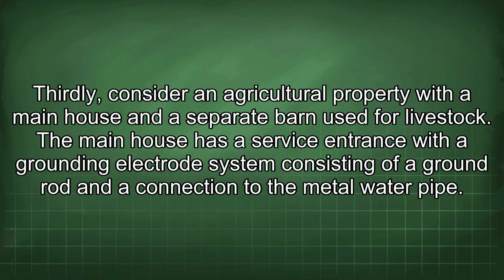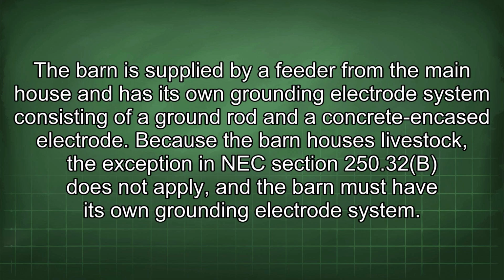Thirdly, consider an agricultural property with a main house and a separate barn used for livestock. The main house has a service entrance with a grounding electrode system consisting of a ground rod and a connection to the metal water pipe. The barn is supplied by a feeder from the main house and has its own grounding electrode system consisting of a ground rod and a concrete encased electrode. Because the barn houses livestock, the exception in NEC Section 250.32(B) does not apply, and the barn must have its own grounding electrode system.